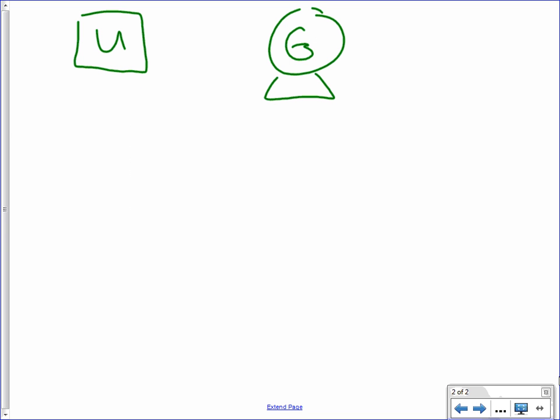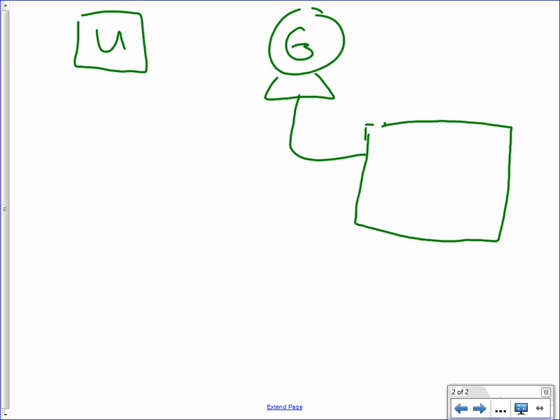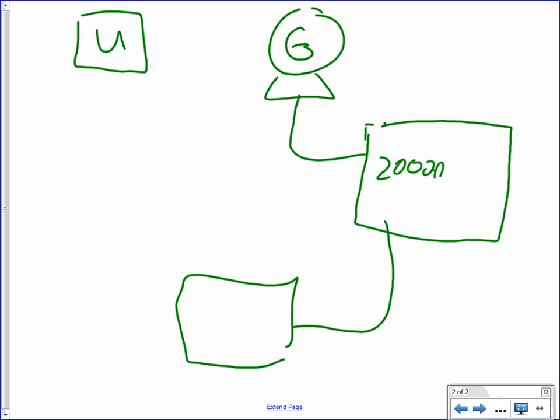And so say we just had one gen, and we're feeding in, we have a main lug only switchboard. So this is Gen 1, right? You're going to have 2,000 amp. Right, because you have two gens, it's a 4,000 amp service. So you're going to have a 2,000 amp breaker, standby power into the utility gear. Now you have this life safety ATS over here, which is 100 amp maybe? Yep. Depends on the building, 100 amp, and you're feeding that.